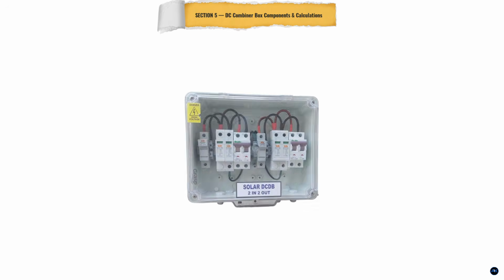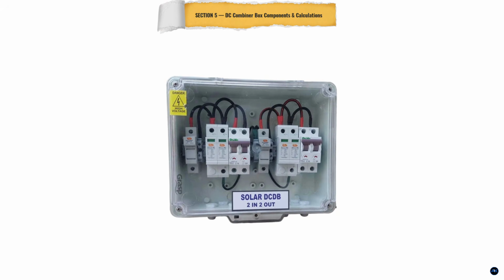Section 5A. DC Combiner Box, Components and Calculations. The DC Combiner Box is where all your solar strings meet before going to the inverter. It protects each string individually and gives you a safe way to isolate the array. Let's go through every component inside and calculate the correct size for each one.